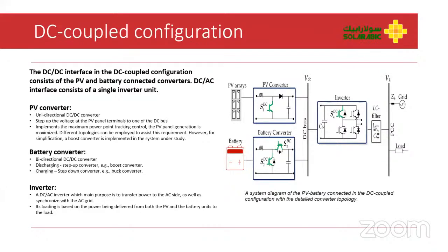In the DC coupled configuration, we normally have two units on the DC-DC interface, the PV converter and the battery converter, and one unit on the DC to AC interface, which is just a photovoltaic inverter. The PV converter here is a unidirectional DC-DC converter. Its major operation is to step up the photovoltaic power from the PV panels to the DC bus bar. The battery converter here is a bidirectional DC-DC converter, operating as a step-up converter during discharging of the batteries and a step-down converter for the charging of the batteries. The inverter is responsible for the DC to AC conversion from these two power sources and also to sync the AC power to the grid. The important point in the DC coupled configuration is that the loading for the inverter is based upon the power from the PV converter and the battery converter.